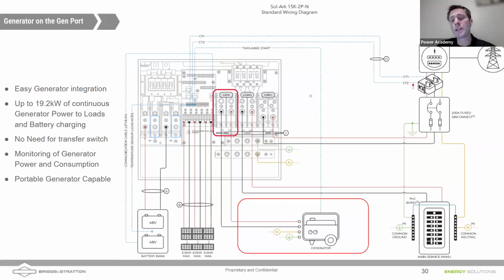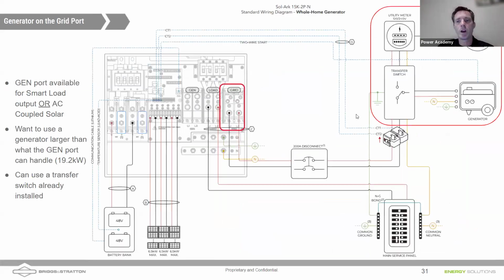Yep. And we do get plenty of customers that have a small, cheap portable that's only capable of, let's say, 30 amps that want to use that. It does have to be a 240-volt generator. So you can't just bring power in on a single leg at 120. You do need to have a 240-volt generator if you want to use a small portable.